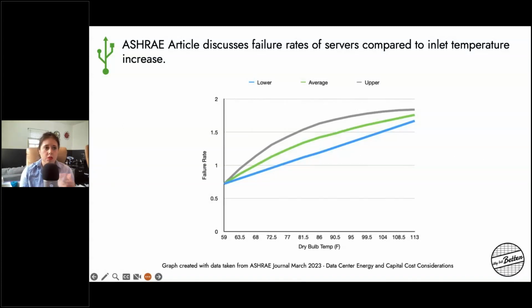This is fairly stable until around year 4, and then you're pushing up to around 11%. This graph shows the result of increasing that inlet temperature from 60 degrees all the way up to over 100 degrees. If you remember from our psychrometric chart, the upper limit of that recommended range was around 80 degrees. So we're really not seeing that failure rate increase all that much.